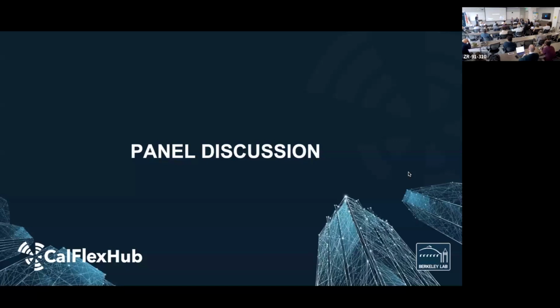But to Ram's point, a couple of things. If you think about new construction and design a building with storage, you can absolutely take down some of the other equipment. You can use storage instead of another chiller and offset those costs. If you're thinking retrofits, it's a different situation because they already have their setup, and you're not going to take down the chiller. You're basically adding additional equipment to what they already have. Yes, they may need less capacity as a result, because during peak time they're not going to be using their chillers. I agree with your point about pre-cooling being more of a control.